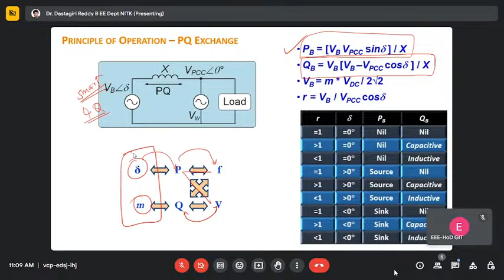So now what we are doing is, irrespective of whether it's converter based or machine based generation, if you control delta, you can control P, whether it's linked to V or linked to F, I don't care. All I want is to control delta so that I can control P. Then I can control the modulation index so that I can control the voltage, and it may control P or Q or anything. So I just focus on these two variables, and that is where I'm going to start my control strategy, not entering into ABC to DQ modes, but a simple load angle or delta control, or modulation index control. Okay, so that's our idea.